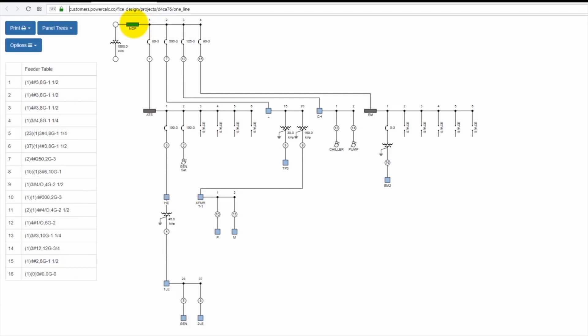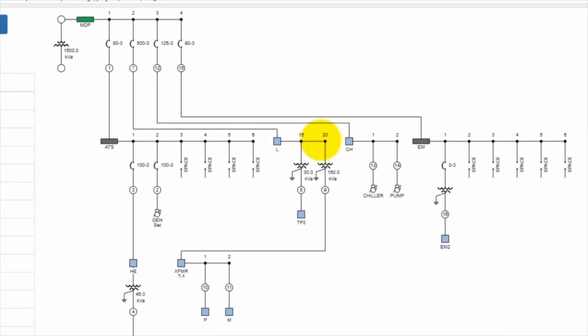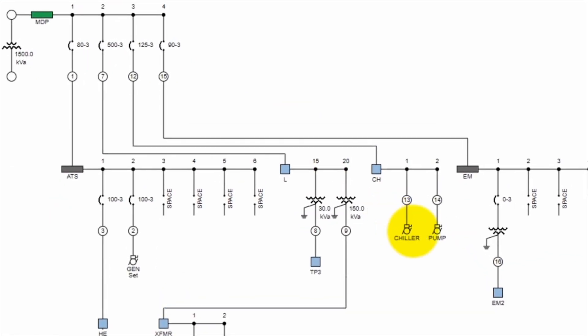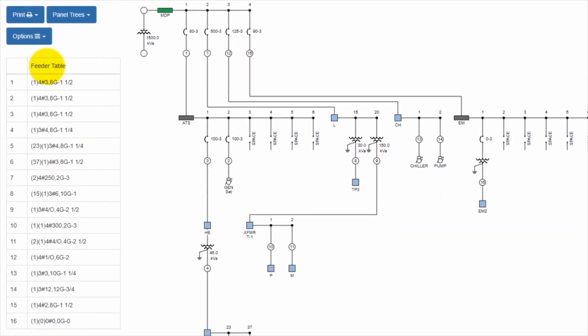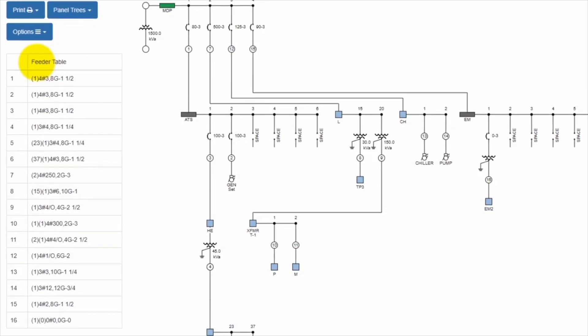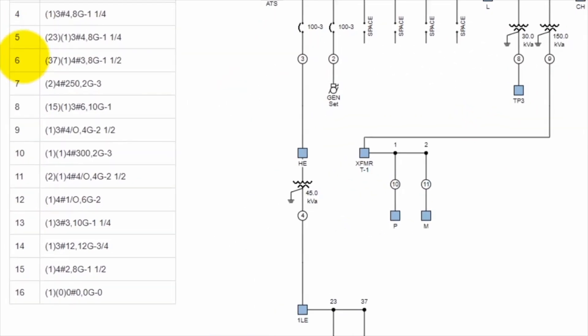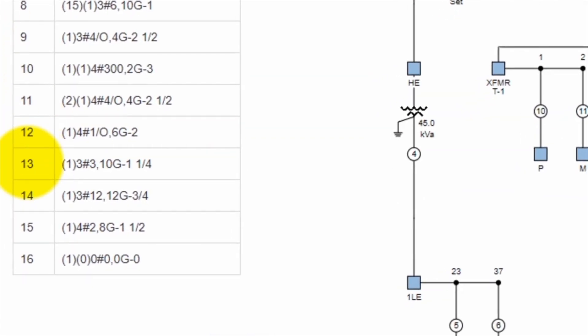Let's take a specific circuit to talk about it a little bit. Let's take the circuit that's going to the chiller, which is circuit number one in panel CH as you can see. Now when you look at the chiller, it has a circle with a number 13 which designates the size of the conductor. On the left side of the one line diagram, you see a chart or table with the conductor sizes associated with these tag numbers. So if you go to the number 13, that feeder for the chiller is one set of three number three and a number 10 ground in one and a quarter inch conduit.